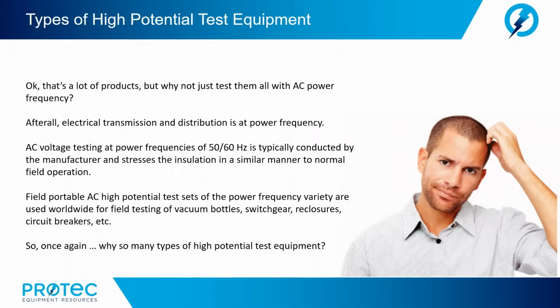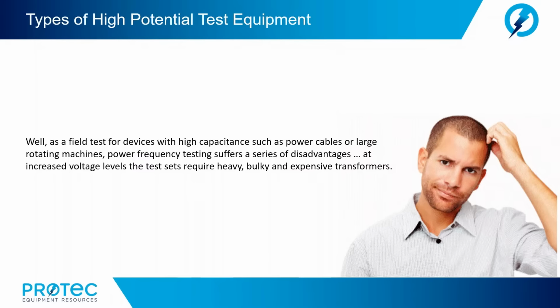So, it brings back that original question. Why so many types of high potential test equipment? Well, as a field test for devices with high capacitance, such as power cables or large rotating machines, power frequency testing suffers a serious disadvantage. At increased voltage levels, the test set requires heavy, bulky, and expensive transformers.